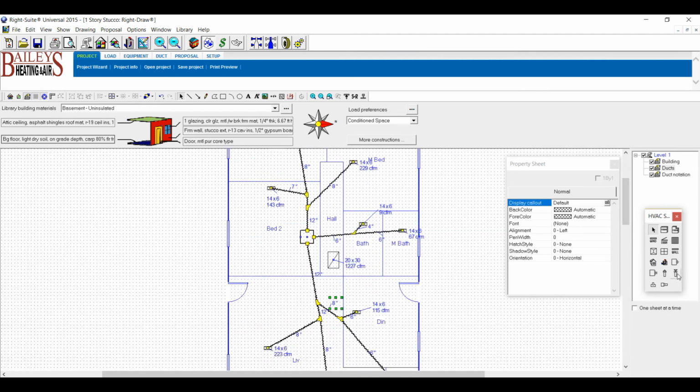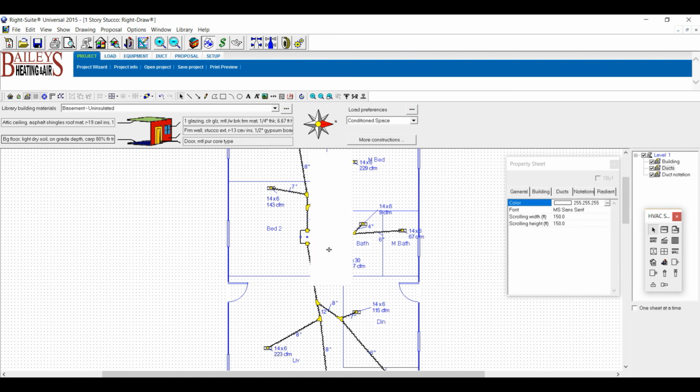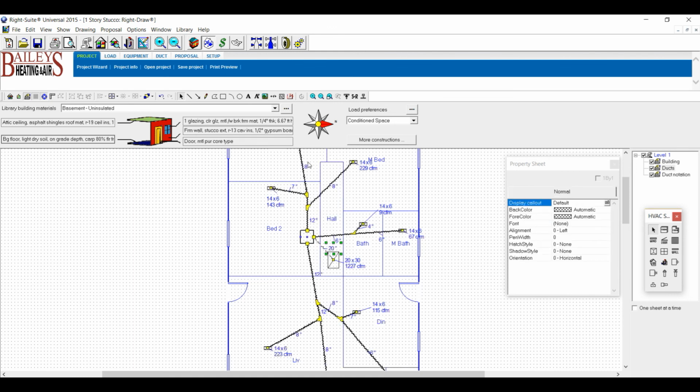Oh, let me do the return. And done the return. What size return do you guys think it is? What size do you think it's going to be? This shows us doing 1400 CFM, right? What size duct? 20-inch. Okay. So it's a 20-inch duct for that return. And then this is designed correctly. I didn't have to do anything else. This didn't take me that long to do. So, you guys, when you do one of these, let's take a look at it. All right. Good luck.